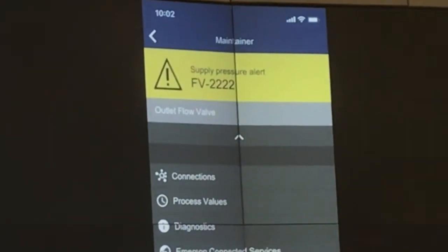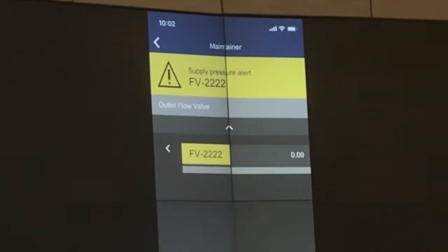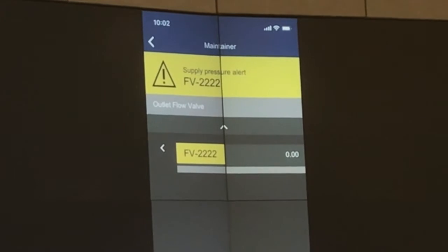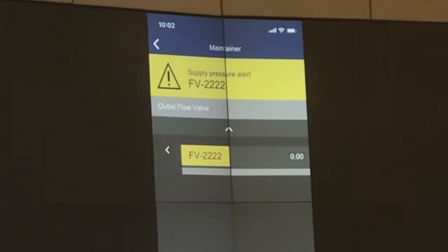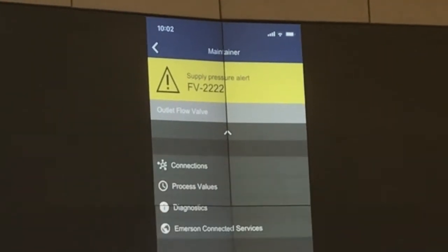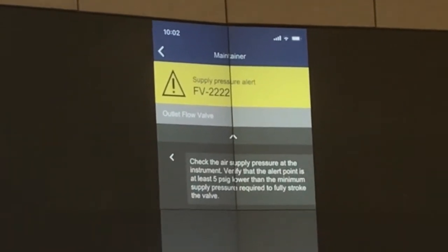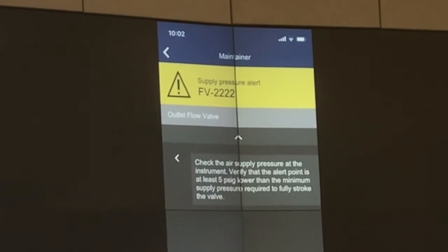On the mobile device, the user can also look at process values coming from the device and can see diagnostic data telling him to check the valve's air supply pressure.